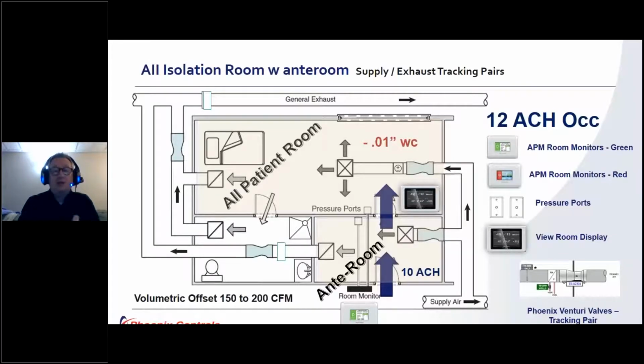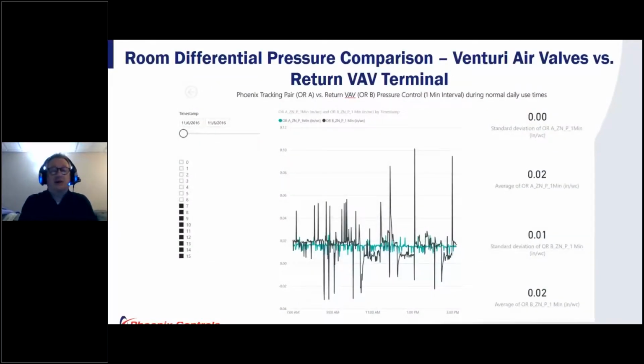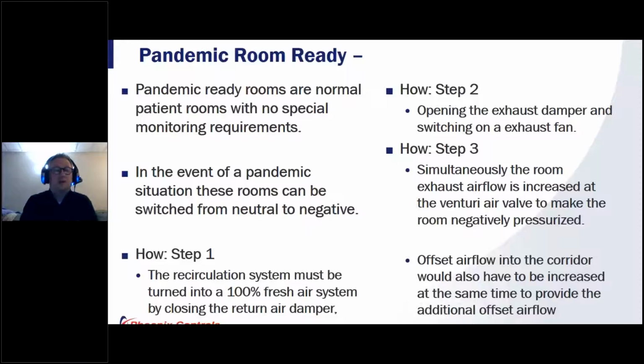And you have your APMs, you have your pressure ports, your room displays, again, all that visual information needed in order to make sure that it's maintaining that direction, that quality all the time, okay? Now, when you look at that room differential that we talked about earlier, this is where it becomes really important, right? There are isolation spaces out there that maintain a constant volume dedicated exhaust in one direction. That still does not negate the pressure differentials that we're seeing and the pressure trips, fluctuations that we're seeing in the ductwork. And again, that can compromise over time the quality of directional flow. And so again, I take you back to making sure that when there's outbreaks, when there's the need for these spaces for what they're originally designed for, good, stable directional flow is key, right? In order to keep the staff safe and keep it from migrating through the public hospital, right?